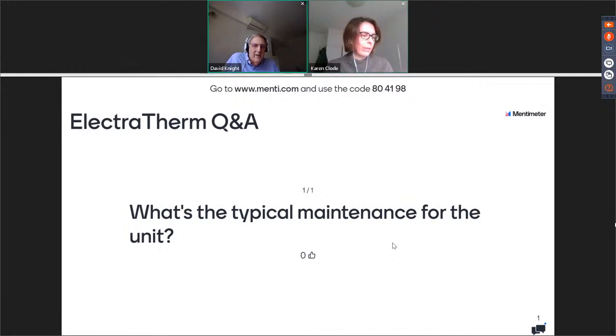We have a full planned maintenance system up, running, and proven, and it's basically done by a fitter. It works on a cycle every 4,400 hours, the initial check basically being for leaks, making sure everything is running correctly, and cleaning the machine. Every 4 years we do a major maintenance on the twin screw expander. So there's a full plan, and it's just a fitter, nobody special. We also offer, for clients who like it, an online monitoring system so we can monitor remotely and tell you the performance figures of the machine and what needs to be adjusted to get the performance up to optimum.